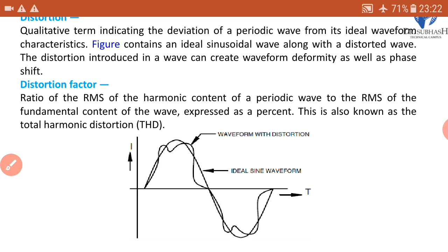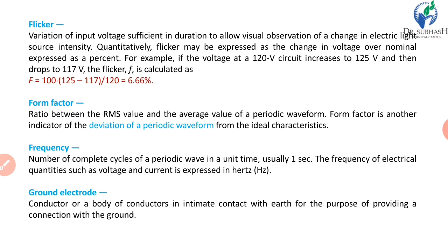Now flicker. It is a variation of input voltage sufficient in duration to allow visual observation of a change in electric light source intensity. Quantitatively, flicker may be expressed as the change in voltage over nominal, expressed as a percent. For example, if the voltage on a 120 volt circuit increases to 125 volt and then drops to 117 volt, the flicker is calculated from this equation. It will be 6.66%. So flicker is nothing but a dim or dip in the light that we can see with our naked eye.